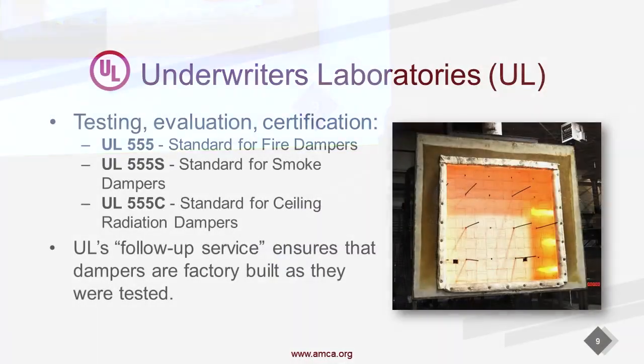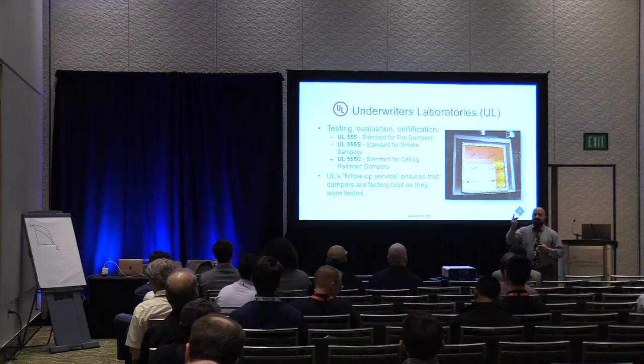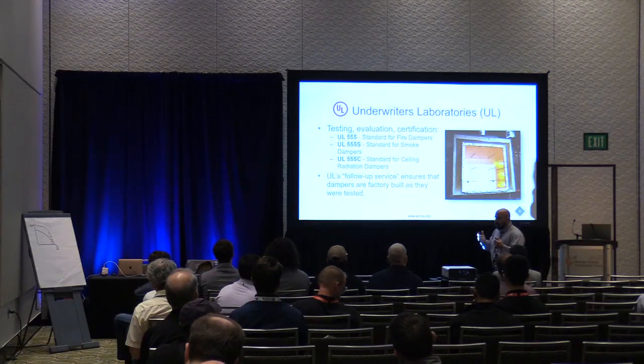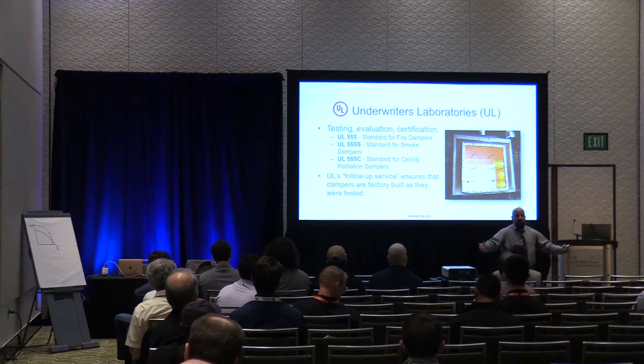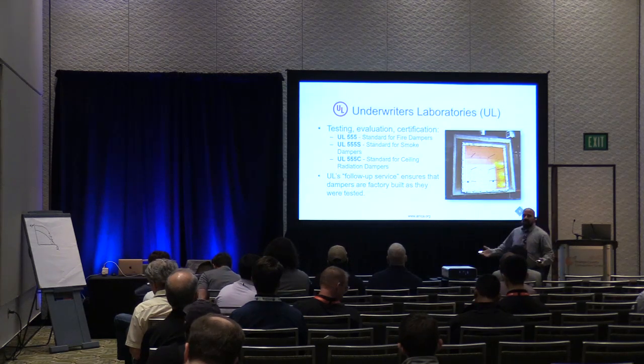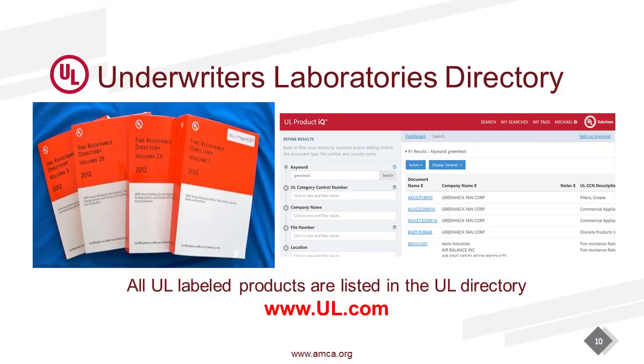Most importantly about UL, they have what's called a factory follow-up service, right? So we build dampers and UL comes into our damper manufacturers' locations and verifies the products we build and ship are the ones we tested and certified, right? We need to ensure the quality in production to ensure the safety of buildings and occupants, right? It's a very important product. Not anybody can just test a damper and start selling fire dampers. You have to meet these very specific requirements. So if you want to verify the UL listing, you go to ul.com, register for their Product iQ, and you can go in and any product that has a UL rating can be found online. And for those of you who were born around the same time, those things to the left, those are called books, but today we just go to www.ul.com.